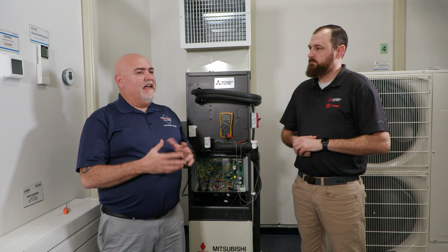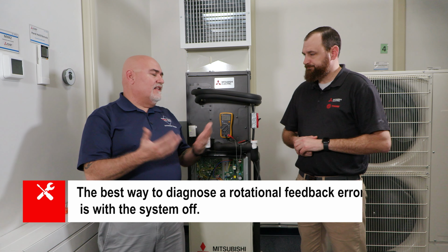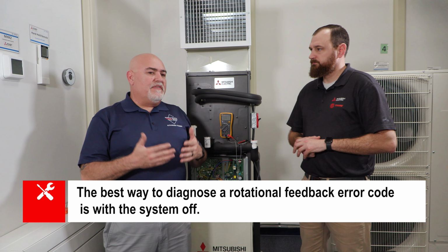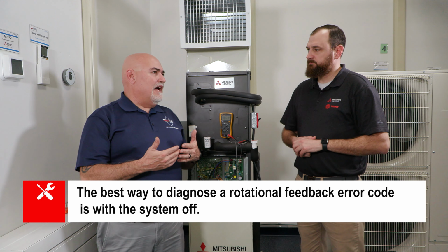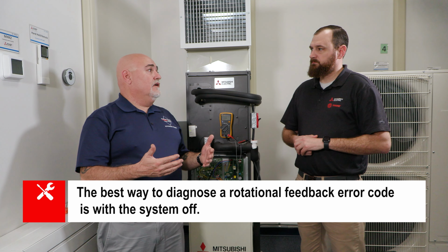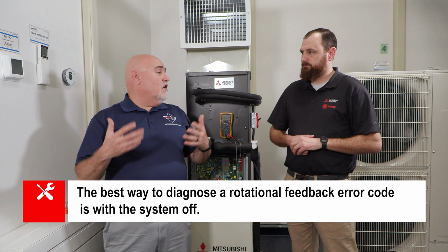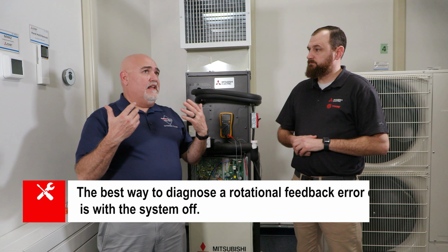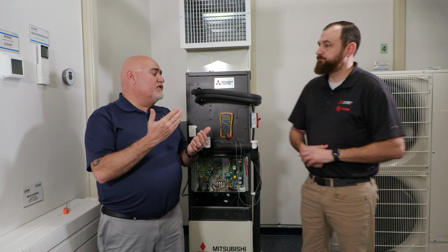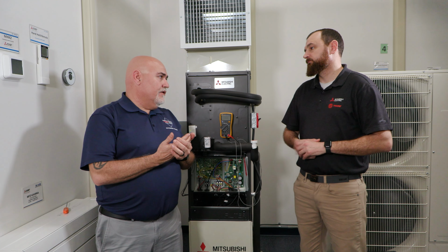Okay. With P-Series, a little bit easier. And as instructors, we've broken this down through a lot of testing in our training rooms, and the best way to diagnose a rotational feedback error code is with the system off. All right, so first, contractors out in the field, they're going to get a fan rotation error code. Number one, and I break this down into 3 steps. First step is they want to clear that error code.